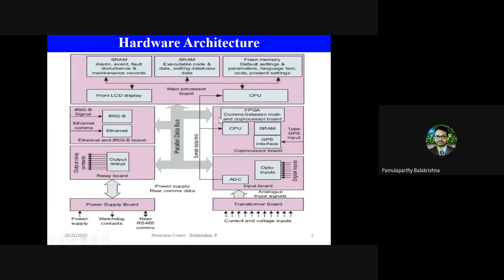Okay, so apart from processors, the other things mainly required for the relays are other inputs in order to smoothly execute the protection as well as the monitoring and control tasks. Apart from the voltage and current inputs, the relay also gets digital inputs and analog inputs, although it is not mentioned here. Digital inputs are basically the on-off status of any equipment or component. For example, a breaker status, whether it is on or off, whether the transformer fan is on or off, or whether the Buchholz relay inside the transformer is on or off. Such status messages, which are binary, are received as digital inputs to the relay.